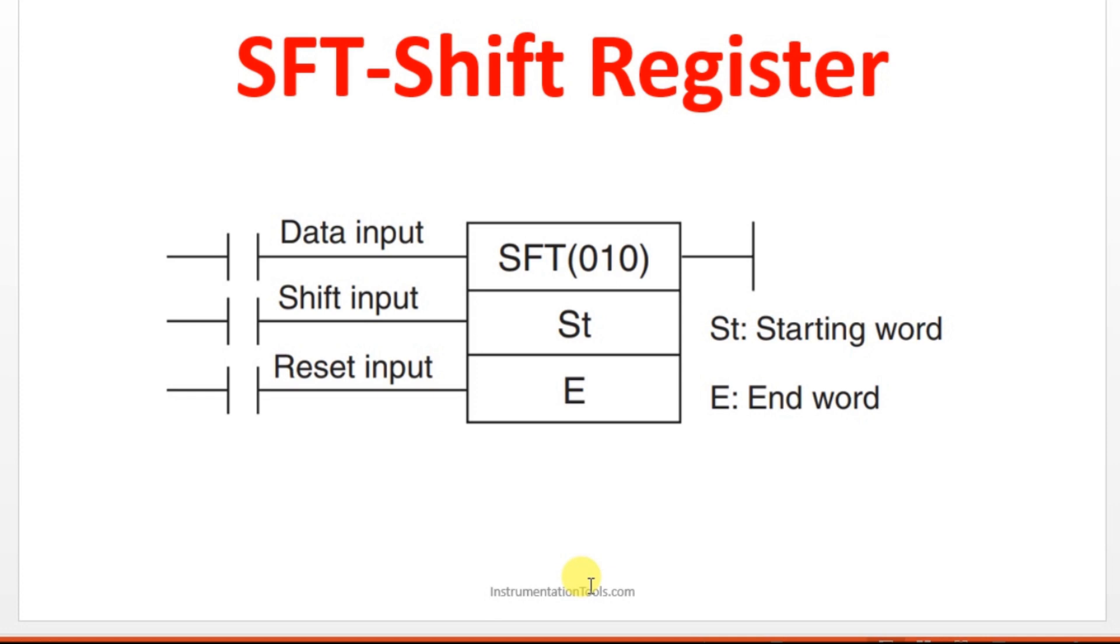SFT is the instruction for shift registers, instruction name for shift register in Omron PLC. Here we are having 5 variables: one is data input, another one is shift input, another one is reset, and we have 2 word addresses which is starting word and ending word.